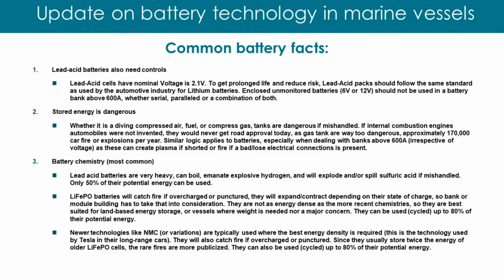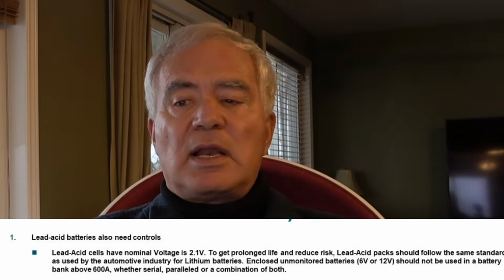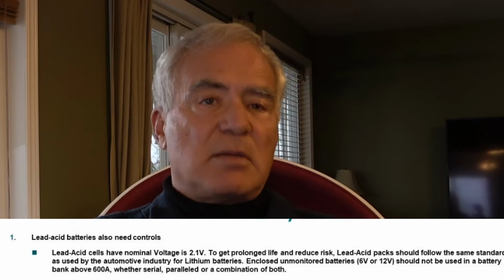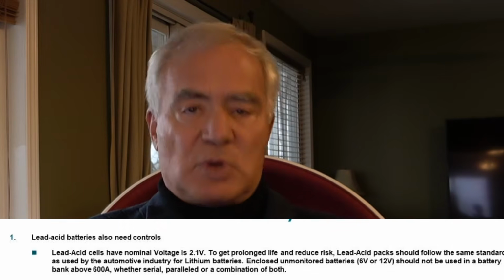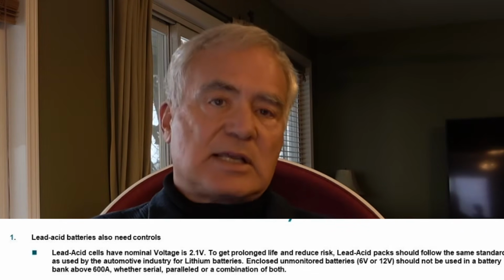And that will also, because it starts to boil, the high voltage cell will start to boil, dissipate some energy, and then the other ones will have time to catch up. And then as soon as you stop the high voltage, the boiling stops, and all the cells are exactly at the same level. But that reduces the life of the battery. Not really, no. They recommend doing it every 6 months or every year on all lead acid batteries, this type of desulfation mode. It's quite an accepted practice. If somebody cares for their lead acid batteries, they can last a long time. And I should also add that if lead acid batteries were properly managed with a BMS, you wouldn't have to change them every 3 months or every 6 months, like it's happening in the charter business, like it's happening everywhere.